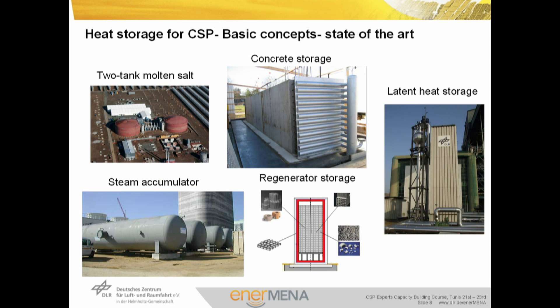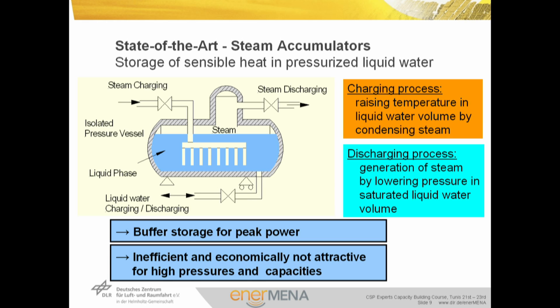There is no single storage concept that can be considered the best solution for all applications. Liquid water is the best working fluid for sensible heat storage below 100°C. To extend the operation temperature, liquid water can be pressurized in steam accumulators, where steam is fed into a pressurized liquid water volume, condensed, and transfers energy. During discharge, saturated steam is provided by the system.